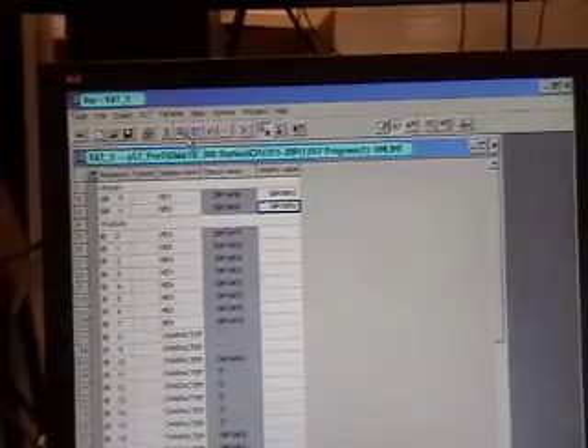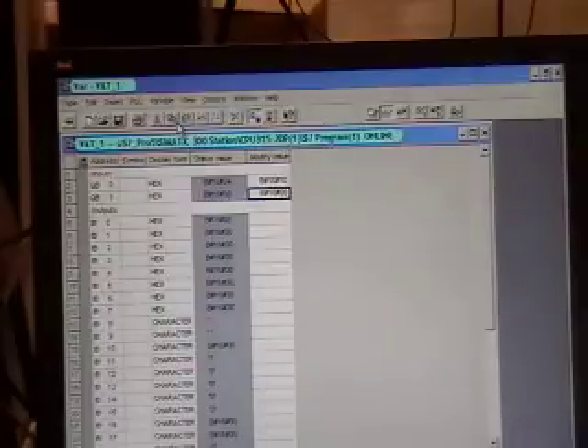As soon as I send it and I realize that the analyzer is in 0 mode, I'm going to have to send another command to go to the sample valve, so when it's finished zeroing, it returns to the sample valve. Otherwise, it will keep going in a loop, zeroing in a loop. So first send this command, then I'm going to send another command for the sample valve. So send this one.